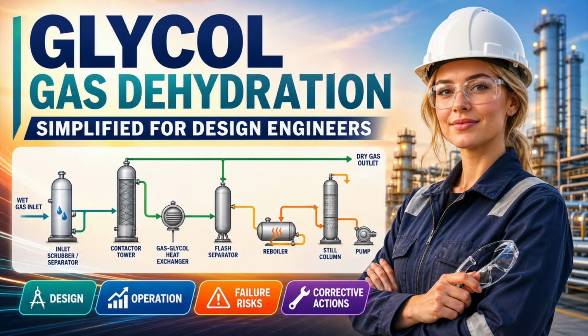The glycol-to-glycol heat exchanger performs two essential duties. It preheats rich glycol before regeneration, reducing reboiler duty, and cools hot lean glycol before it reaches the pump and contactor. If the exchanger fouls, bypasses internally, or operates with poor temperature approach, fuel demand rises and lean glycol enters the absorber too hot. This is a good example of system interaction. One exchanger affects energy efficiency, pump conditions, and absorption performance at the same time.